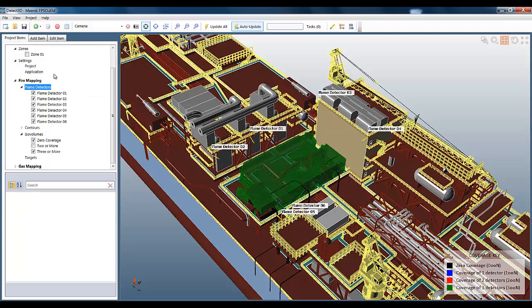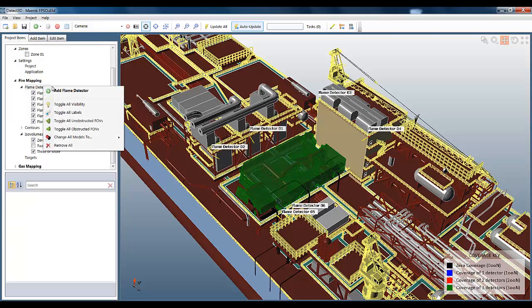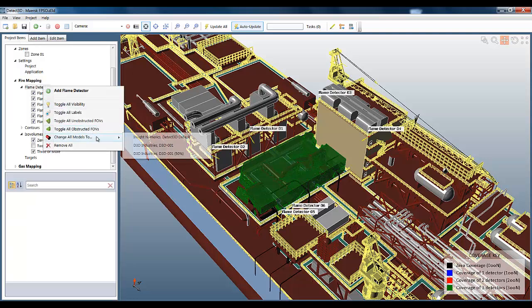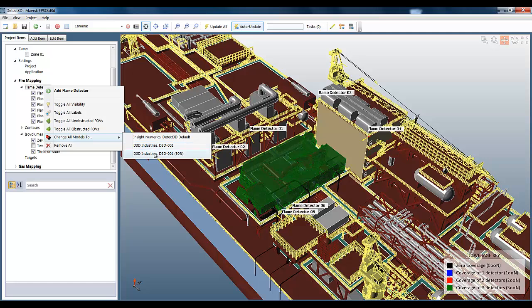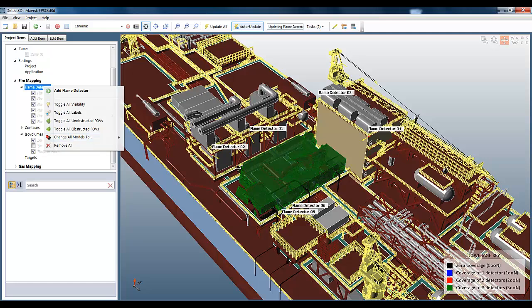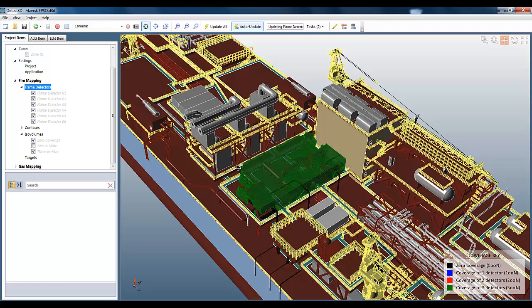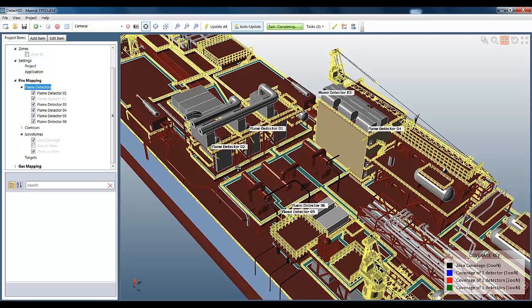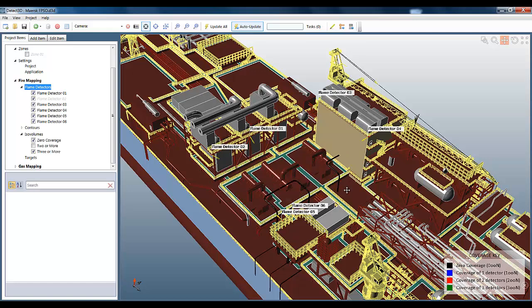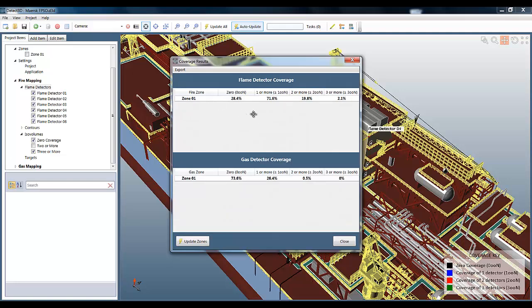Back to the project, I can now change all flame detector models to the 50% range, and the project is now all updating. You'll be able to see the iso-volumes automatically update, and we expect the green to go down, and the black to increase. And we can see that here. The zero coverage is much greater, and the coverage of three or more is much reduced, and that's obviously reflected in the coverage statistics for the fire zone.